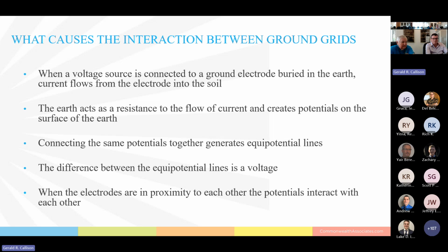So what causes the interaction? Well, when a voltage source is connected to a ground electrode that's buried in the earth, current flows into the electrode and into the soil, as Gerry described. The earth acts as a resistance to that flow of current and creates potentials on the surface of the earth. If you take the magnitude of the potentials and connect them together, we end up with what we call equal potential lines. That's a voltage between equal potential lines. And when the electrodes are in proximity to each other, they interact.